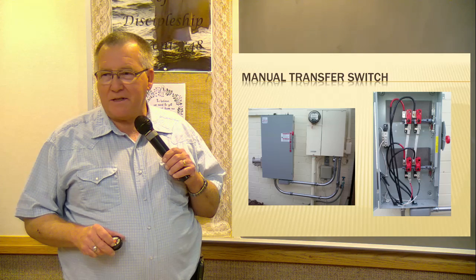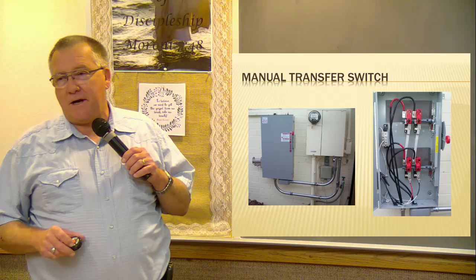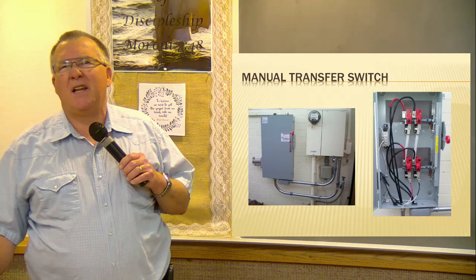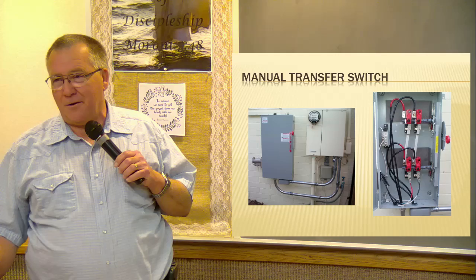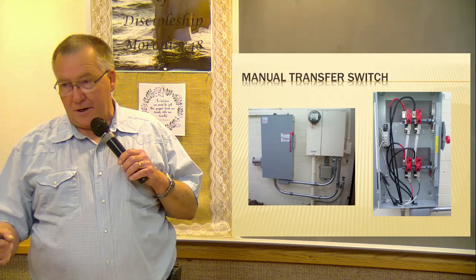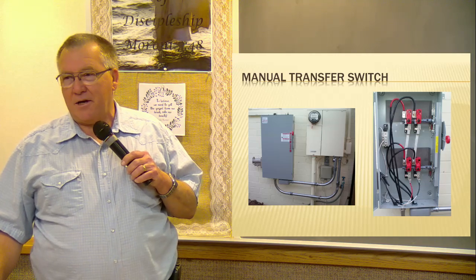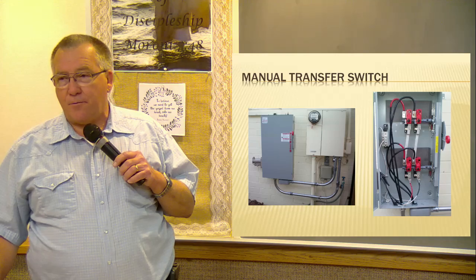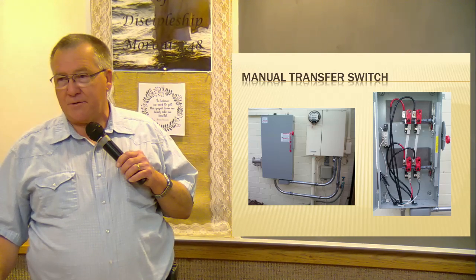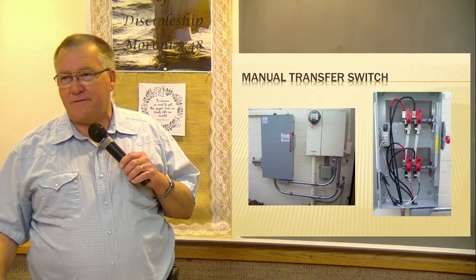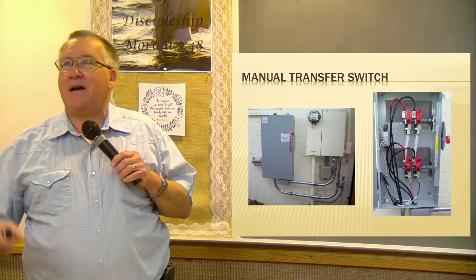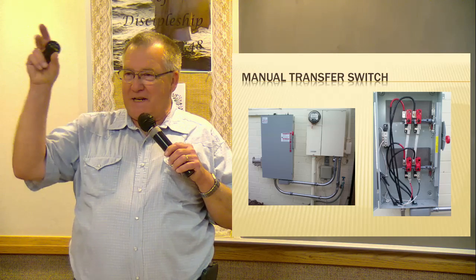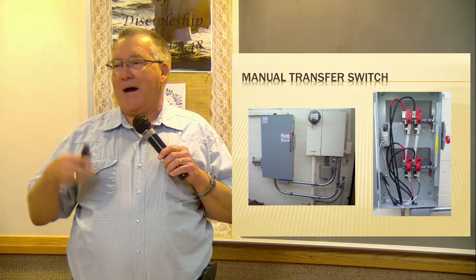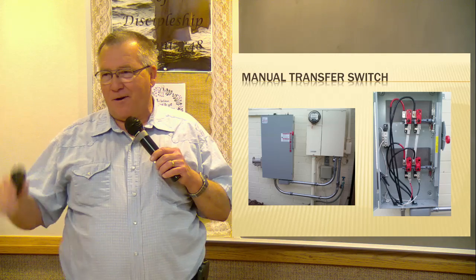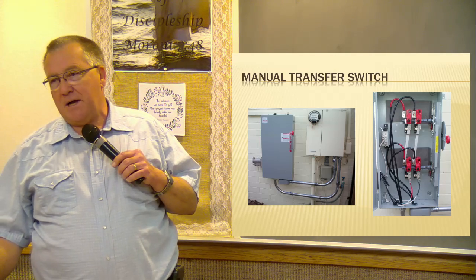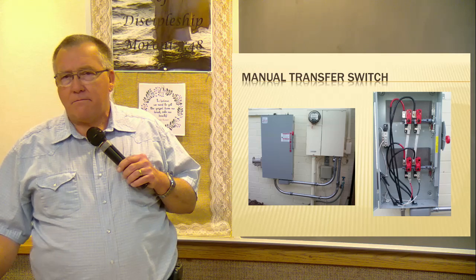Just put the whole house on it. A three-ton air conditioner is going to take at least a minimum of a 9-kilowatt generator to start it. That's the problem with air conditioners - typically 3 times the run power is required, but only for a fraction of a second to start it. Notice how sometimes when the air conditioner comes on, the lights dim for a moment - that's the power the compressor is drawing on the start winding, typically 3 times the run power.